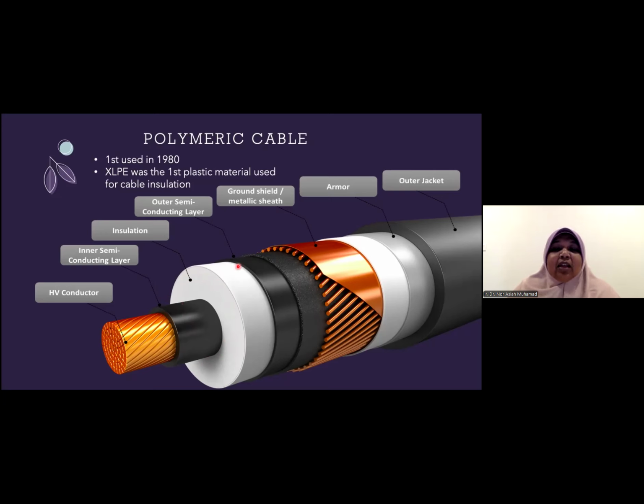Then we have the outer semiconductor. Then we have the shielding, which is for electric field distribution control. Then we have the armor, and the outside is the outer jacket, mostly made from rubber. XLPE was the first plastic used in power cable, and it's been used until now. It is a very good cable for underground power cable from 11 to 66 kV.